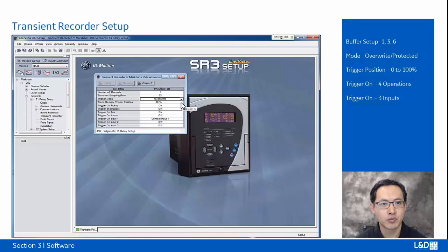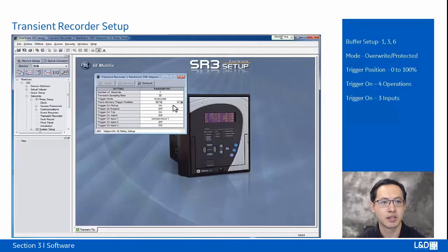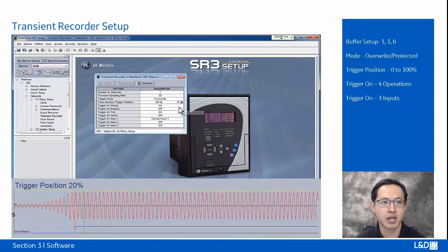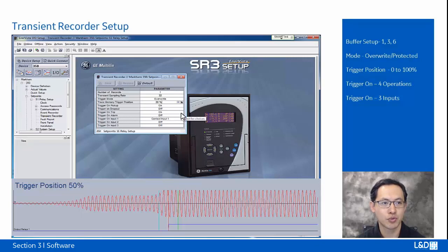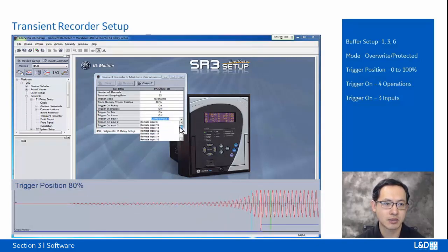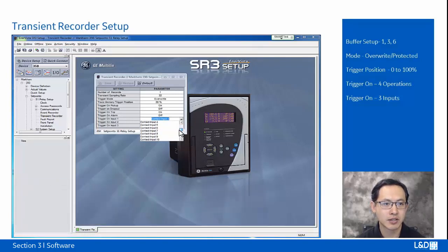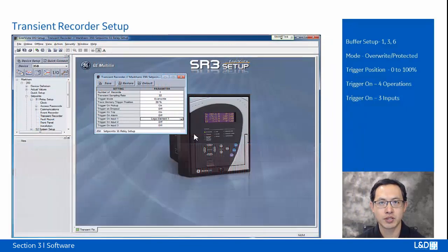And the waveform triggering position can be set from 0 to 100%. And we're using 20% here. And trigger can be done by 4 operations of pickup, dropout, trip, and alarm. And also by 3 inputs. These 3 inputs can be set into 4 different digital input types that are remote inputs, contact inputs, virtual inputs, or logic elements. So in total we can have 12 digital Boolean inputs to trigger this waveform, plus the 4 operations. So that's the setup for the transient recorder.